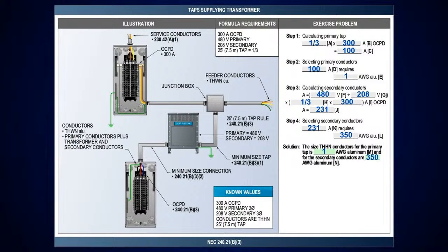So as you can see, it doesn't matter what you're doing, which conductors you're using here. All you have to remember when you're doing these calculations is if it's 10 foot or less, divide by 10. Everything else, take at a third. And if I have a transformer in the tap, I've got to get the ratio of the transformer on the secondary. That's it. Okay?